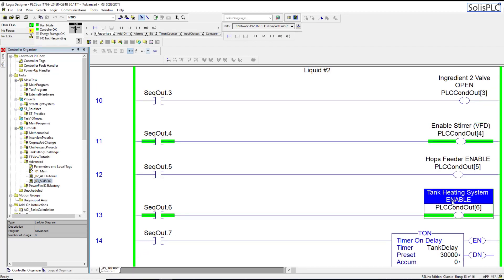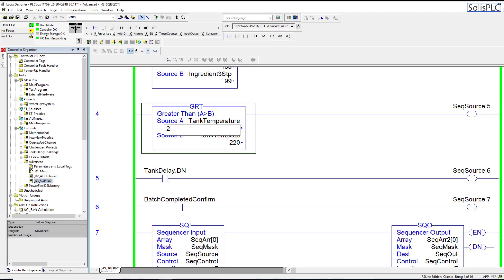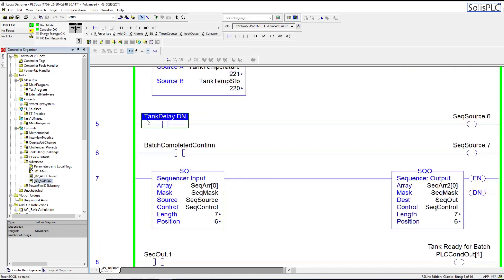The tank level is at 100 percent, meaning we cannot add any more ingredients. At this point we need to keep stirring and heat the mixture. The mixture in the tank needs to be heated to a set point of 220 degrees Fahrenheit. The temperature starts rising - 100 Fahrenheit, 200 Fahrenheit, and at some point it becomes 221 Fahrenheit. At that point we need to heat the tank for 30 seconds. This timer can be changed, but once those 30 seconds are done we've heated enough of the mixture.